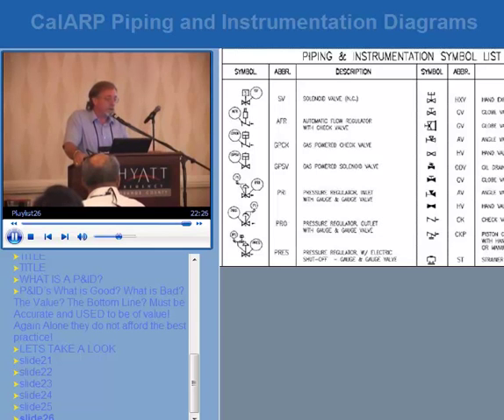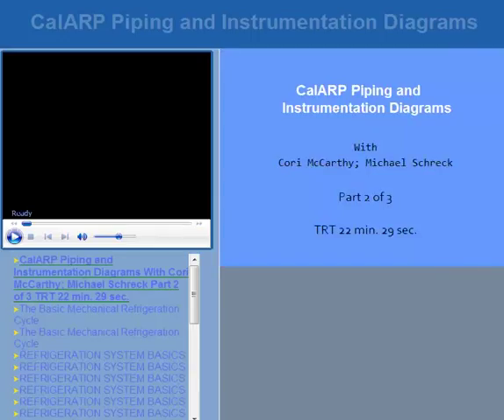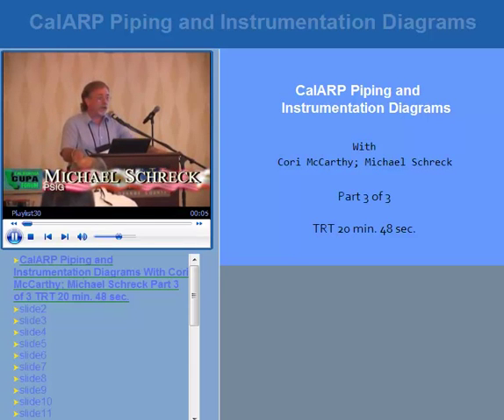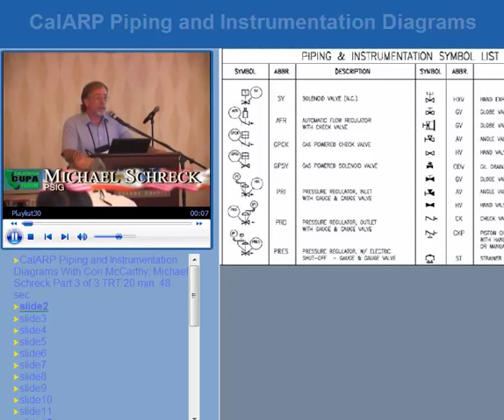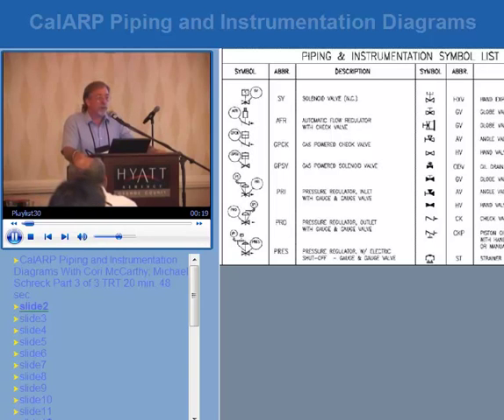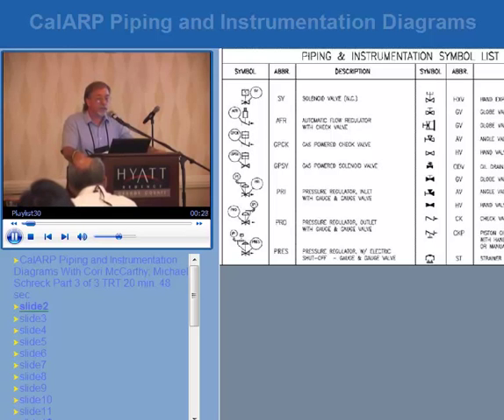Under CalARP there's a new standard for system entry. Cal-OSHA is now requesting a written program for system entry — to enter the system safely and make sure the ammonia has been removed and pumped out. If you don't have accurate P&IDs, there's a chance you may miss a branch line or an automatic line and get exposed. In system entry, we write down the valve numbers and tag the valves to their normal positions, then remove those tags returning the valves to normal position when done.